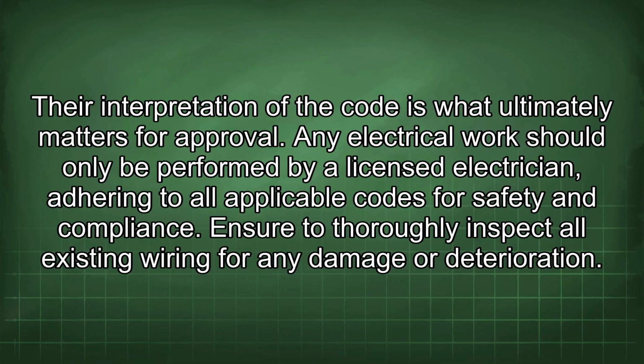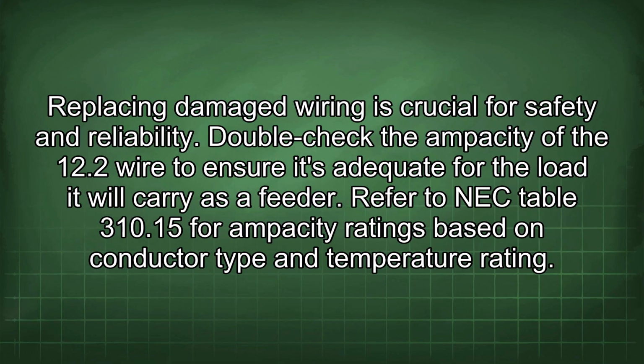Ensure to thoroughly inspect all existing wiring for any damage or deterioration. Replacing damaged wiring is crucial for safety and reliability. Double-check the ampacity of the 12.2 wire to ensure it's adequate for the load it will carry as a feeder. Refer to NEC Table 310.15 for ampacity ratings based on conductor type and temperature rating.